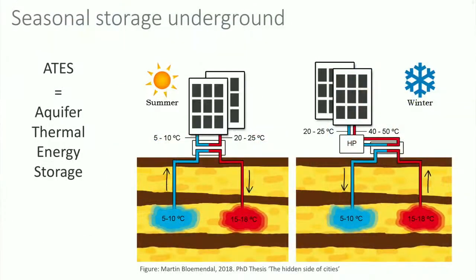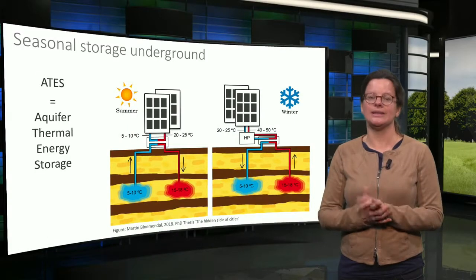In winter the reverse happens. Warm water from the warm well is extracted to be used for heating the building. Since the water storage usually has a maximum temperature of 25 degrees, a heat pump is used to further upgrade the temperature. The cooled groundwater is injected into the cold well again. On an annual basis, the heat and cold extracted must be in balance.